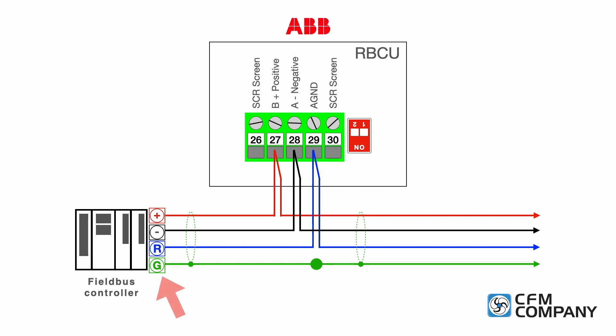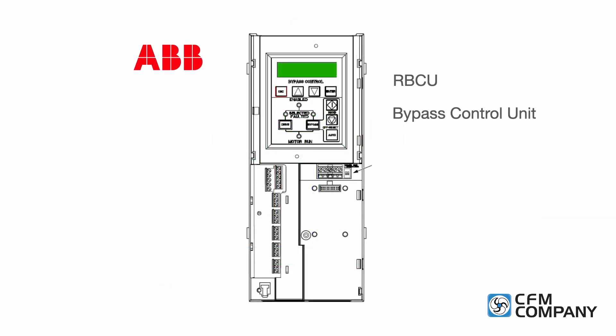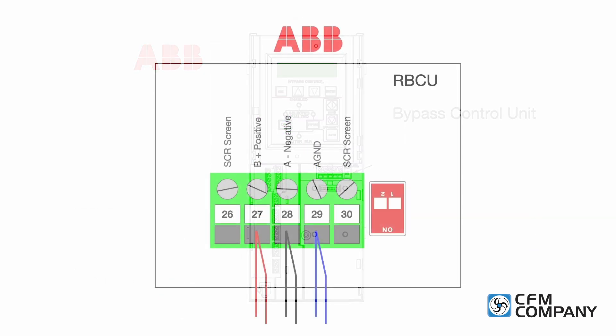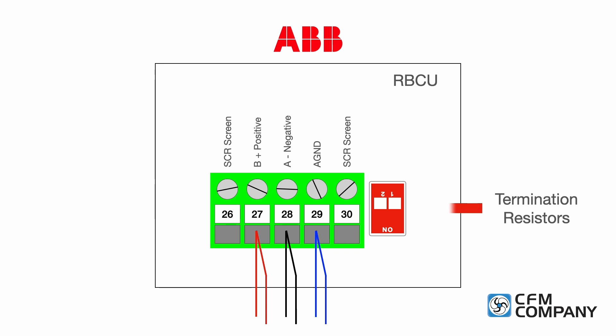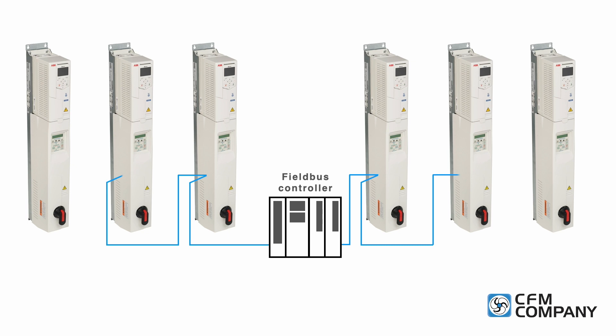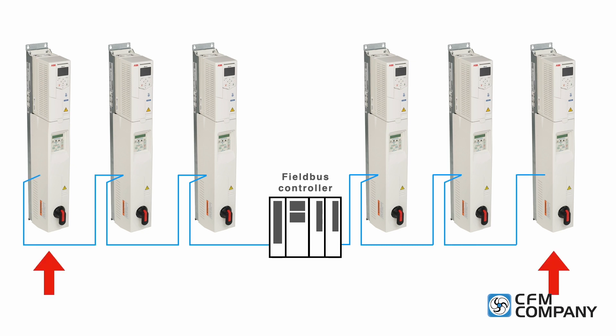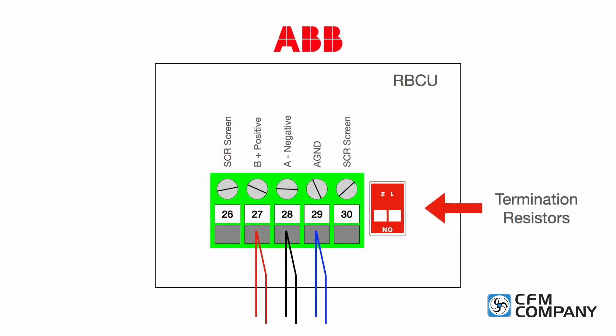The wire shield should be twisted together and taped to prevent contact with other conductors. Terminate the shield only at the ground terminal in the building automation controller. The bypass control unit, RBCU, includes a dip switch used to configure the serial communications termination resistors. To reduce noise on the serial communications network, terminate the EIA-485 network using 120 ohm resistors at both ends of the network. Use the dip switches to connect or disconnect the onboard termination resistors. Both switches must be positioned in the on or off position to correctly configure the termination resistors.